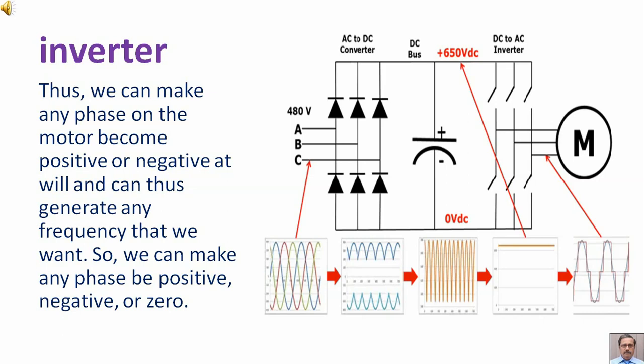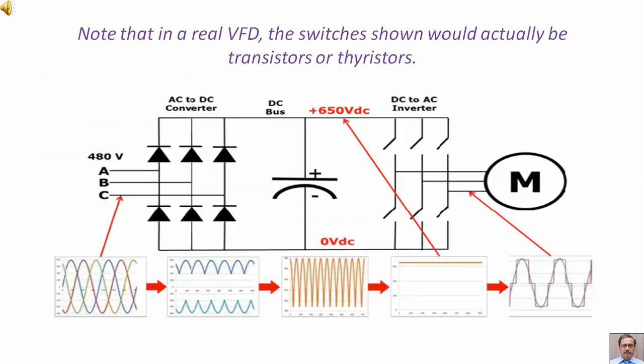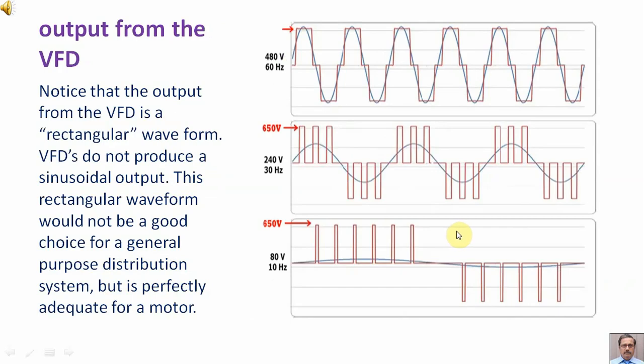Thus we can make any phase on the motor become positive or negative at will and can thus generate any frequency that we want. So we can make any phase be positive, negative, or zero. Note that in a real VFD, the switches shown would actually be transistors or thyristors. The output from the VFD is a rectangular waveform. VFDs do not produce a sinusoidal output. This rectangular waveform would not be a good choice for a general purpose distribution system but is perfectly adequate for a motor.